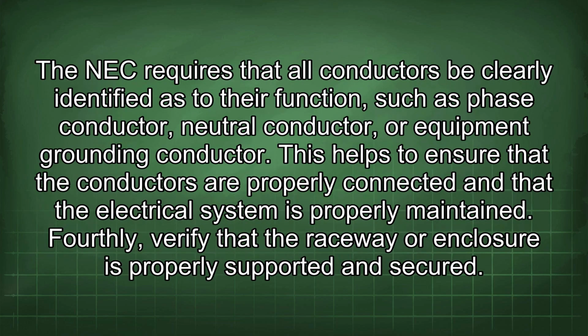The NEC requires that all conductors be clearly identified as to their function, such as phase conductor, neutral conductor, or equipment grounding conductor. This helps to ensure that the conductors are properly connected and that the electrical system is properly maintained.